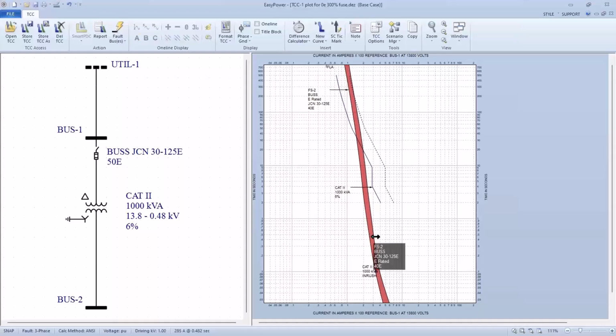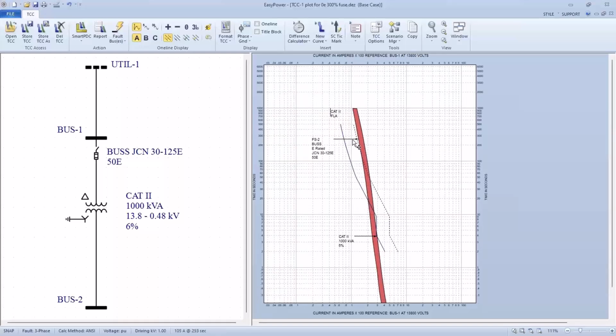So it's up to the engineer to decide whether we take a chance and make sure we get secondary coverage to cover the single line to ground fault, which if we put this here, my single line to ground according to this is going to trip the fuse protecting the primary. But I still have a large exposure to lower current, and frankly, I'd be curious how the philosophy that the audience would take as far as secondary protection. So the point I'm trying to make, even though the NEC tells me I can use a fuse as large as this, does my system really protect itself for lower faults, and what's the possibility of those lower faults occurring that I need to be aware of?